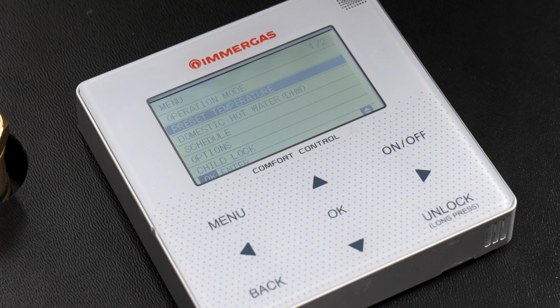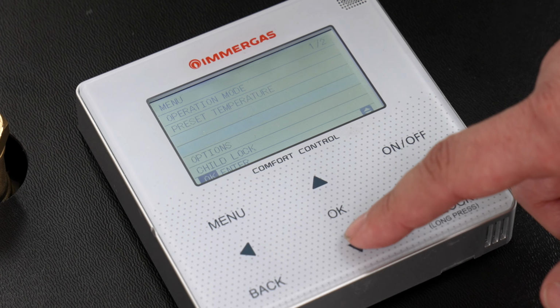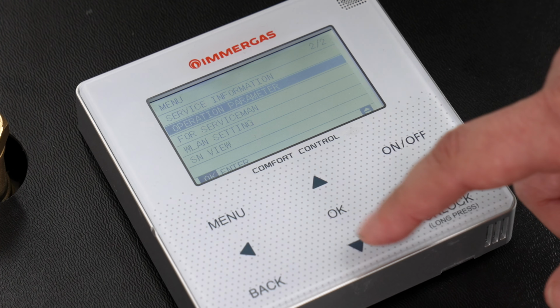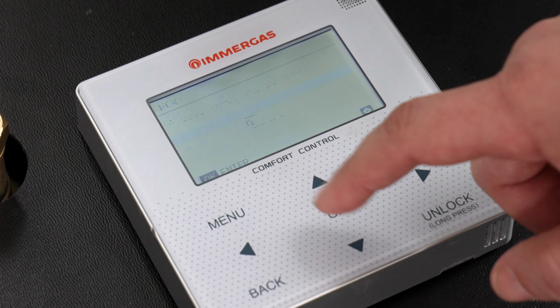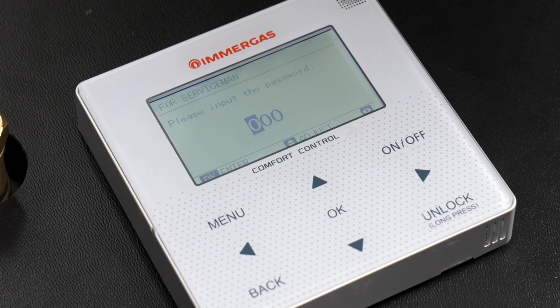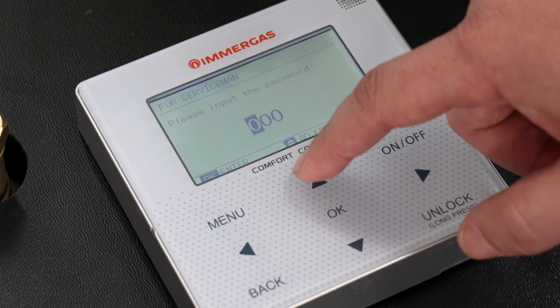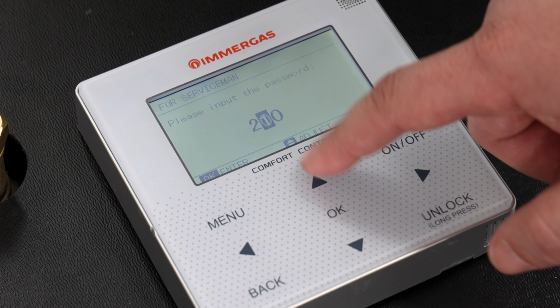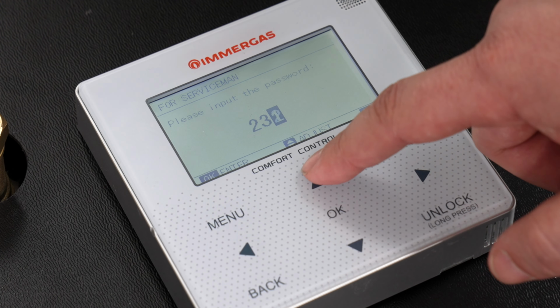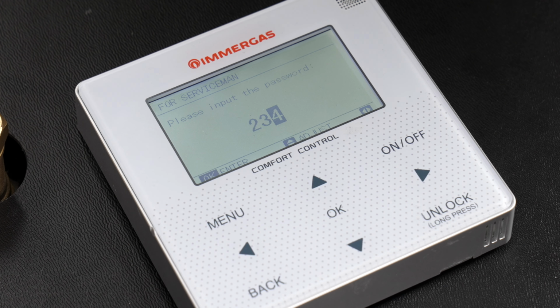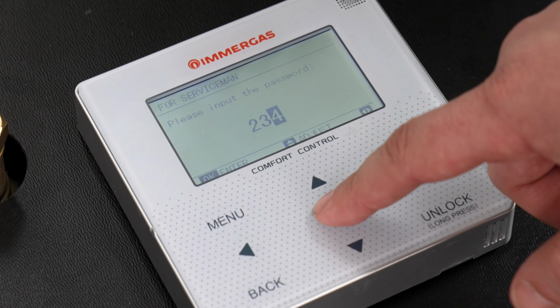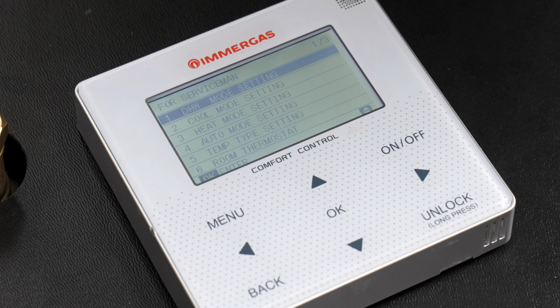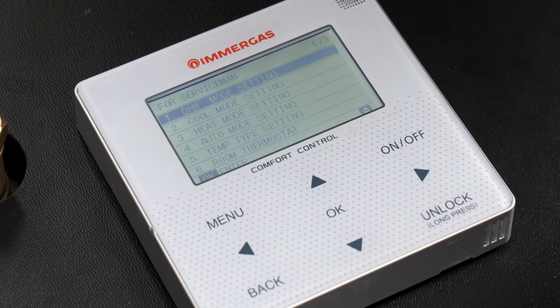The next menu we're looking for is through the screen until you come to serviceman, and then we press OK. Now the password that you're looking for anytime you use the controller is 234. Once you've inputted the password, again if you press OK, it now gives you a full list of different things that you can alter on the controller. The first one we want to do is make sure that the hot water setting is on.